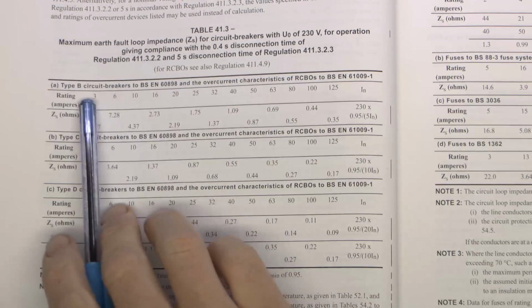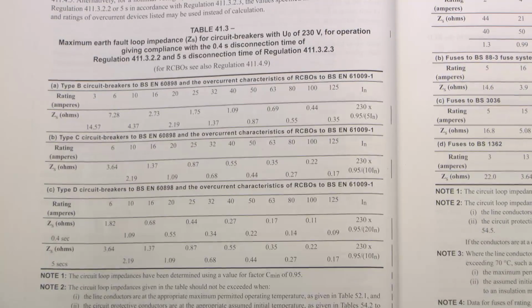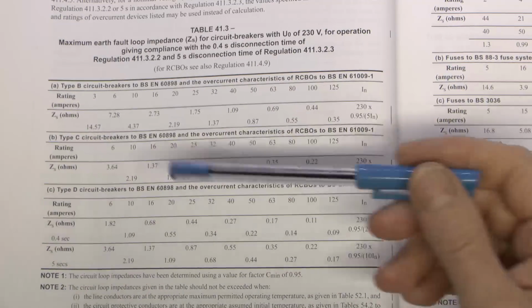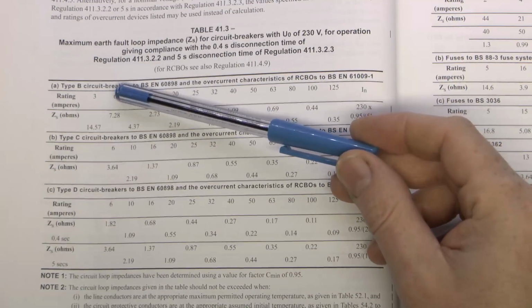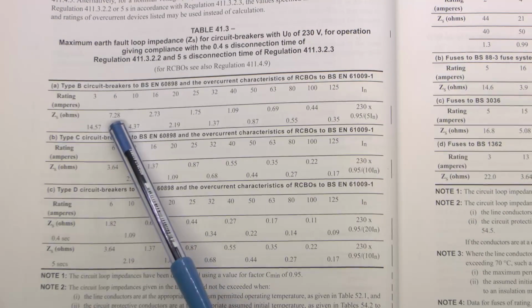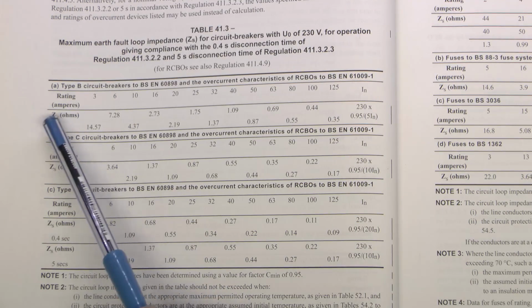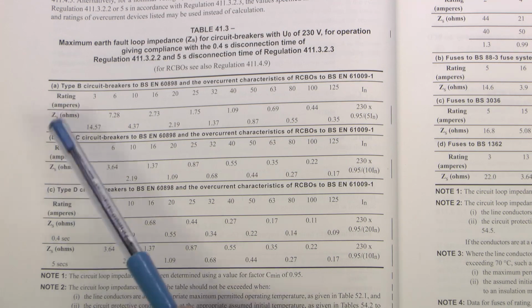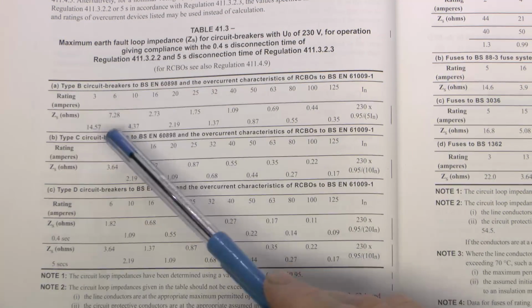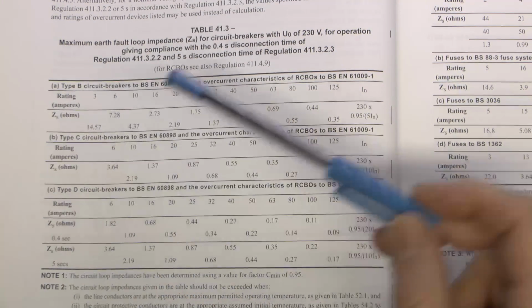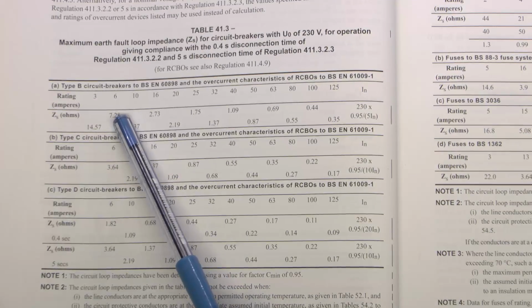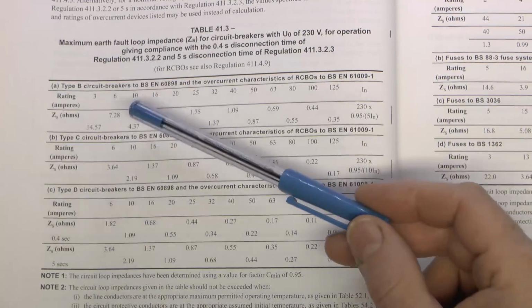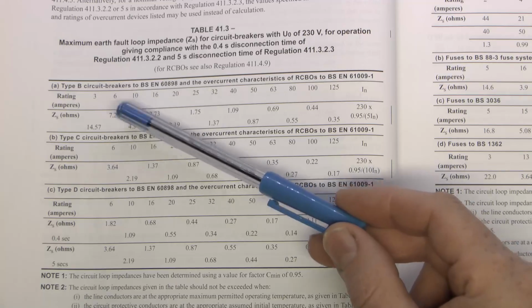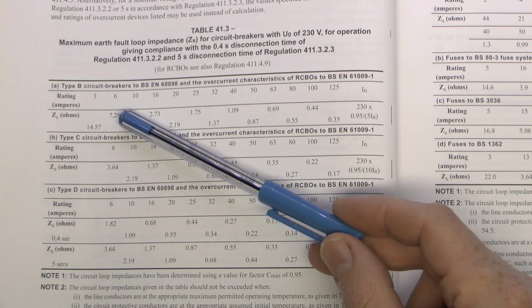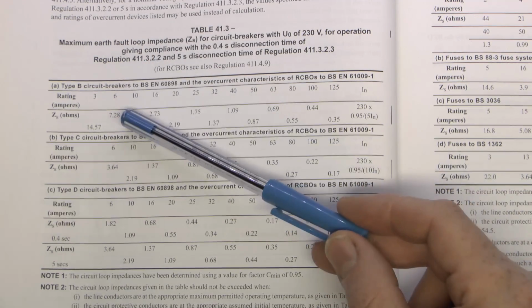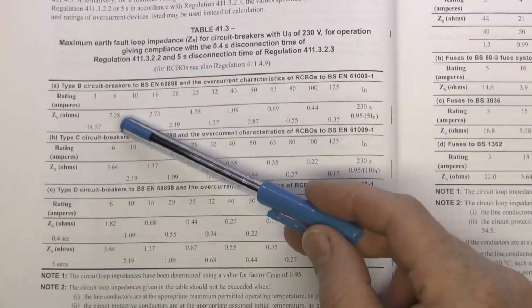So you can see along the top here, got various ratings, starting from 3 going up to 125. And if you have a look at that 6 amp one, so similar to what we were just using there, and then this here giving the total impedance, or Zs, so that's the external impedance and the impedance of the circuit itself. And these are actually the maximum values you can have. So at the top here we've got type B, which is, say, the most common. So for a 6 amp circuit breaker, the maximum impedance is 7.26 ohms. So that's actually pretty easy to get to. Not really going to be a problem.